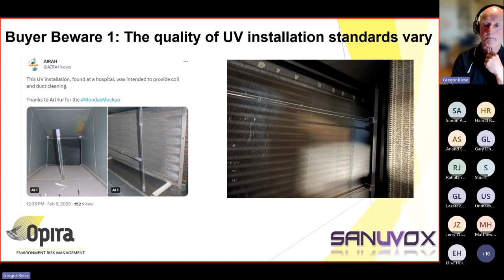The other part about the unshielded, I touched on the parabolic mirrors earlier. If you have an unshielded UV in an air handler, it will affect anything that's plastic, so the power line to this particular fan motor will be destroyed eventually. It'll get brittle and fall apart. Also, the damage to the powder coating is quite noticeable in this particular installation. So again, it makes sense, doesn't it?